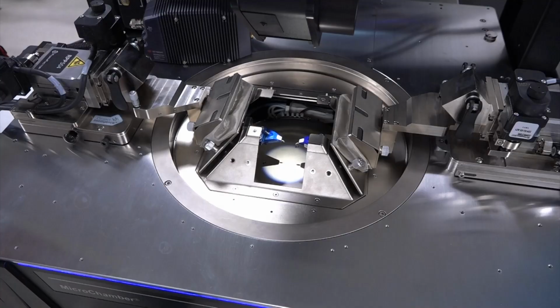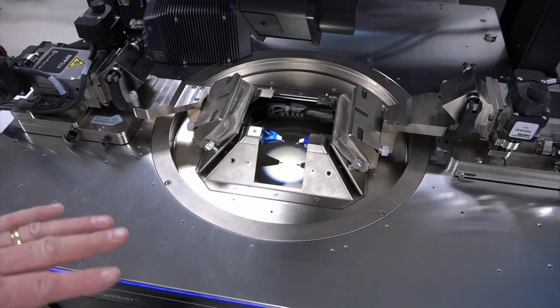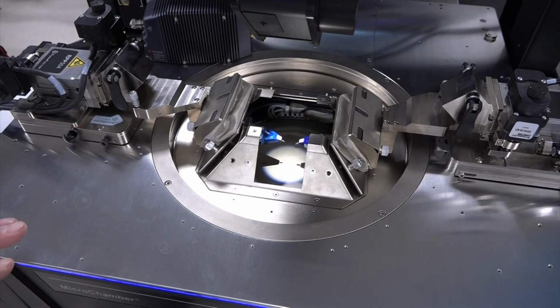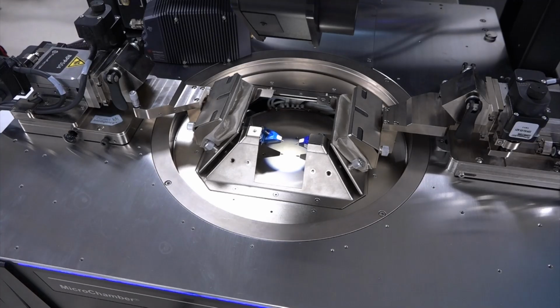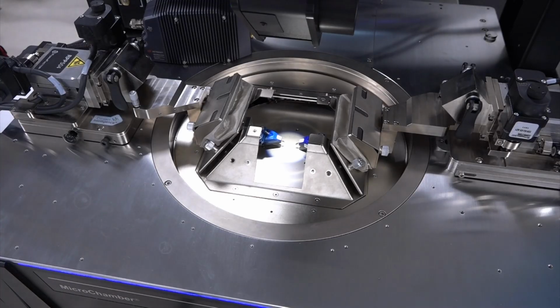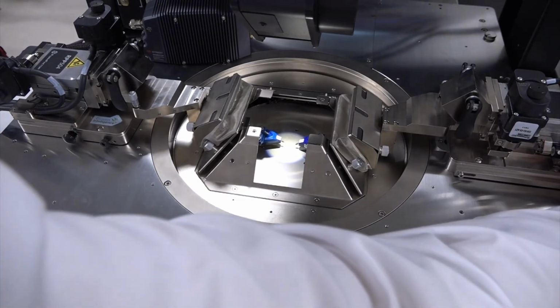Okay, so before I lock all the positioners down, I want to make sure that the probes can physically overlap. So on the wafer prober, I'm going to press the center button. That's going to move to where the center of the chuck is. So that's in the center. With platen levers up and the positioner controls all the way up. And I'm going to go up to my old contact height, which is what I had with the wafer on earlier. Oh no, it's been unloaded, so it's going to take it all the way up like that, so we can see what's going on. Doesn't need to be that precise here. And with both probes retracted.